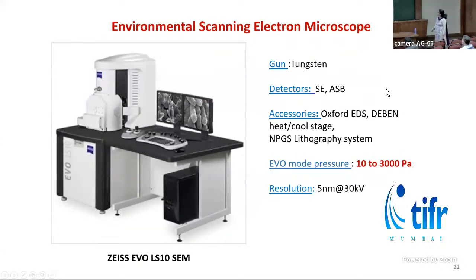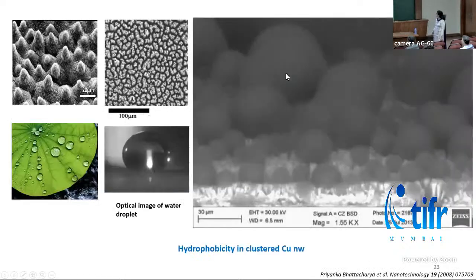This is an environmental SEM. It has a tungsten filament, and it can also go to a pressure of 10 to 3000 Pascal, and hence, by using a couple of pressure limiting apertures, we can image biological samples or wet samples using this machine. This has a resolution of 5 nanometers at 30 kV. Here are some examples of samples imaged using ESEM.